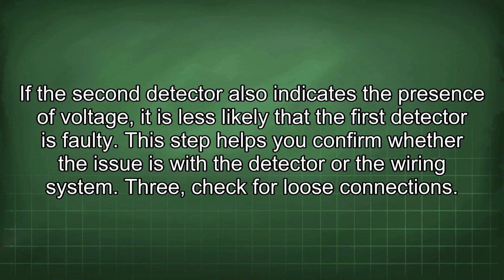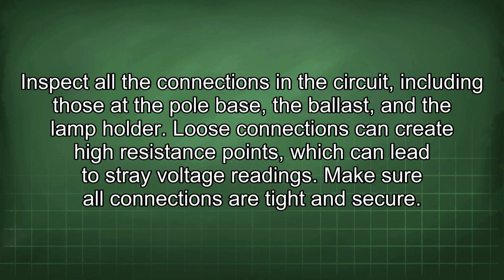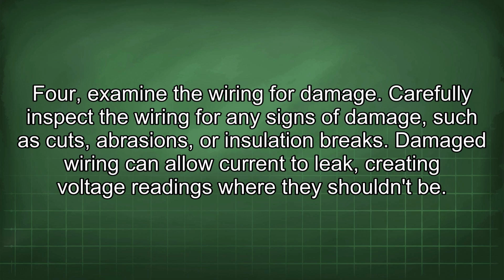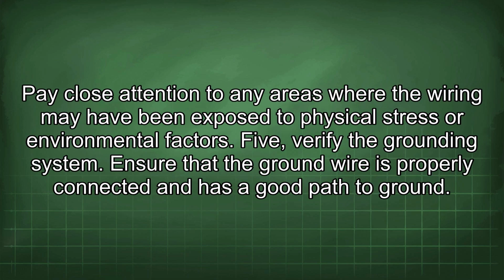3. Check for loose connections. Inspect all the connections in the circuit, including those at the pole base, the ballast, and the lamp holder. Loose connections can create high resistance points, which can lead to stray voltage readings. Make sure all connections are tight and secure. 4. Examine the wiring for damage. Carefully inspect the wiring for any signs of damage, such as cuts, abrasions, or insulation breaks. Damaged wiring can allow current to leak, creating voltage readings where they shouldn't be. Pay close attention to any areas where the wiring may have been exposed to physical stress or environmental factors.